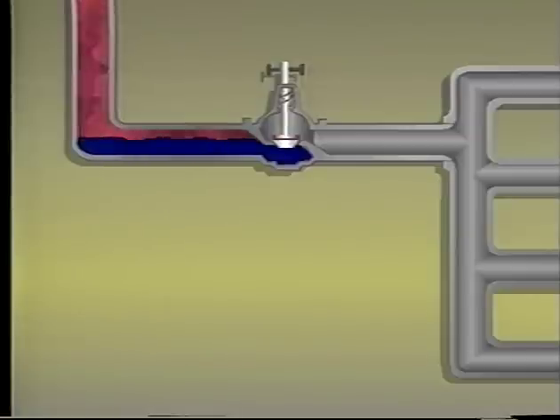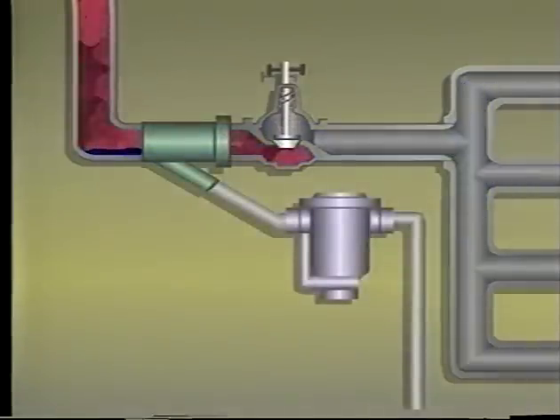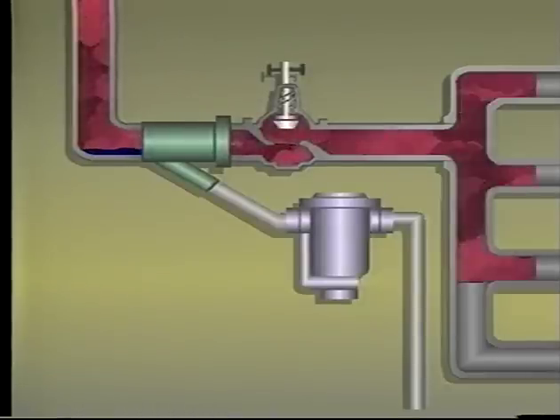When the valve is opened, the slug of condensate is driven through the valve and into the piping and equipment by the live steam. The placement of a riser and a drip trap immediately upstream of the control valve will prevent this rampaging slug.